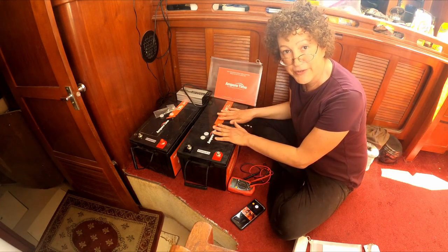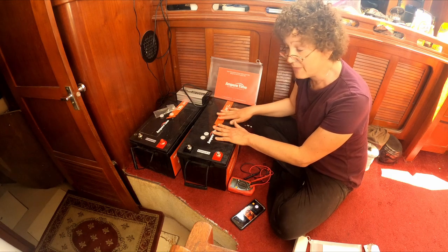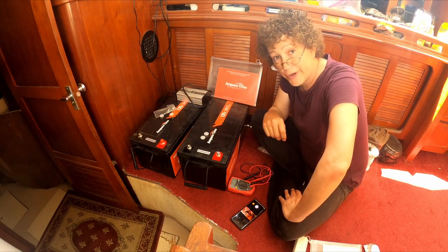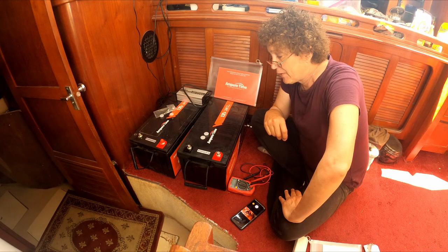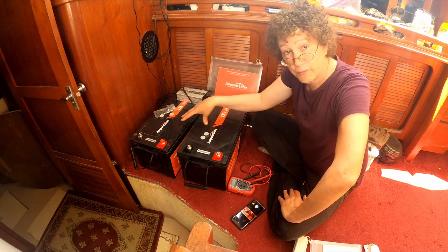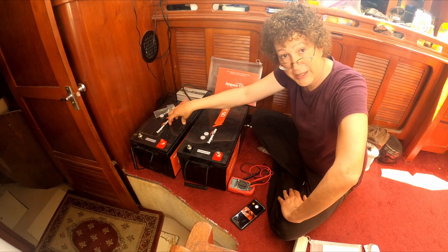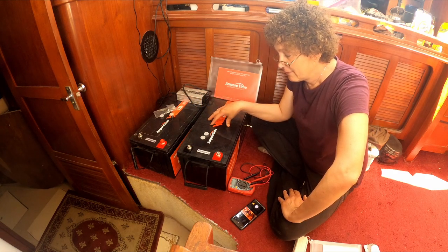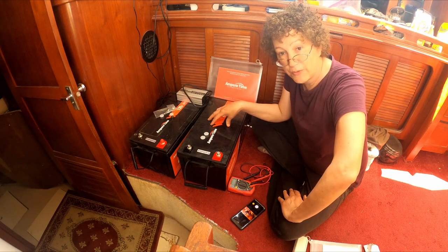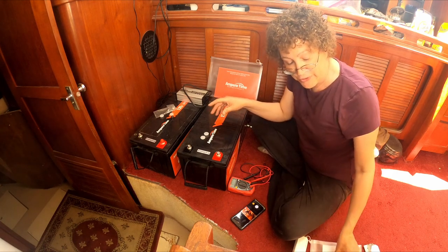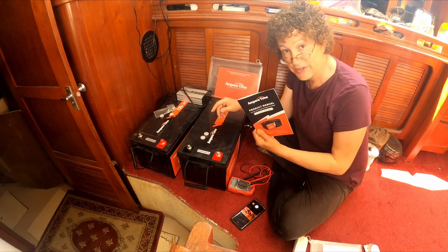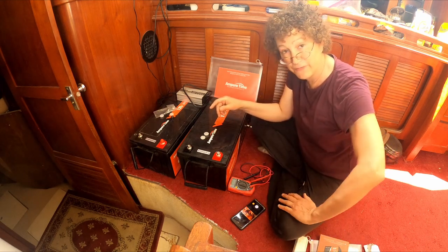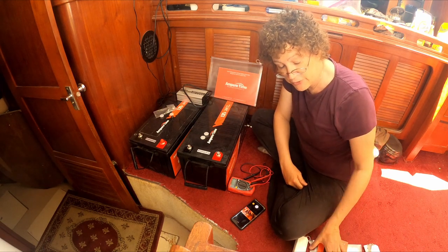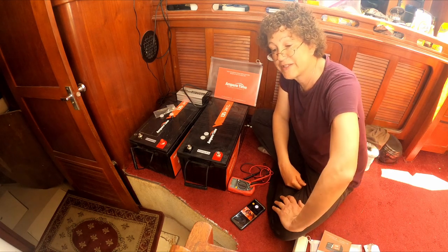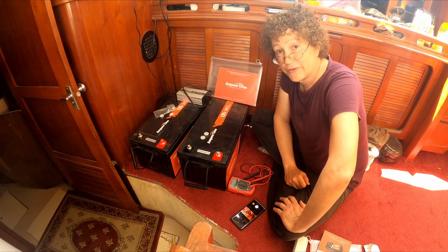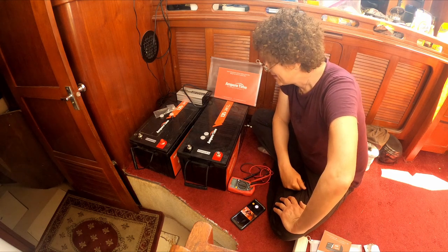Before we connect these batteries up, we have to charge them. They come from the factory partially charged. The voltage on both of them was within 0.2 volts of each other - this one reading at 13.2, and this one at 13.18. The batteries need to be charged according to the manual to 14.6 volts, pushing through 14.6, which will then settle back to about 13.7 after the charge cycle is completed.